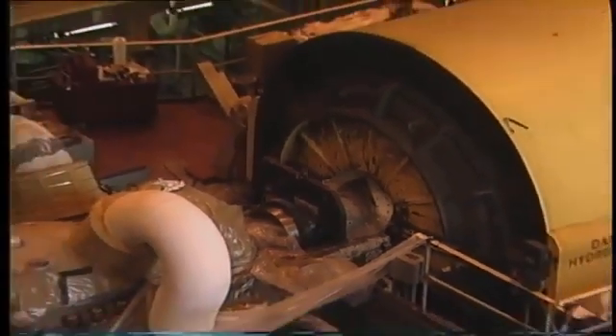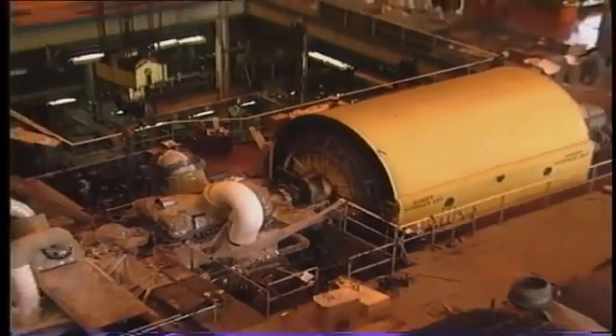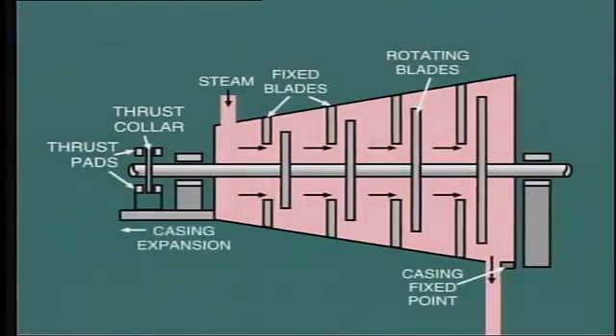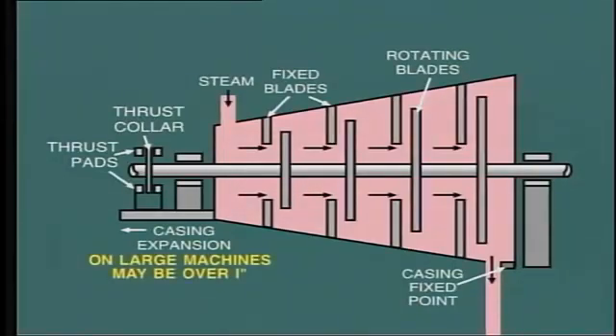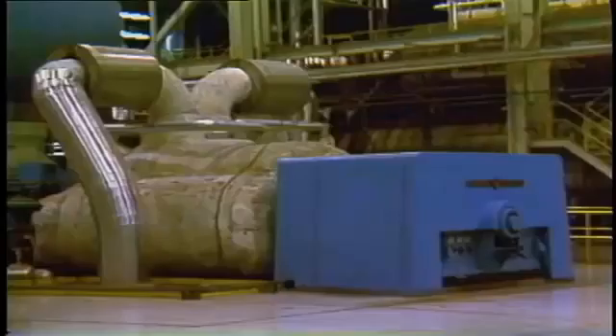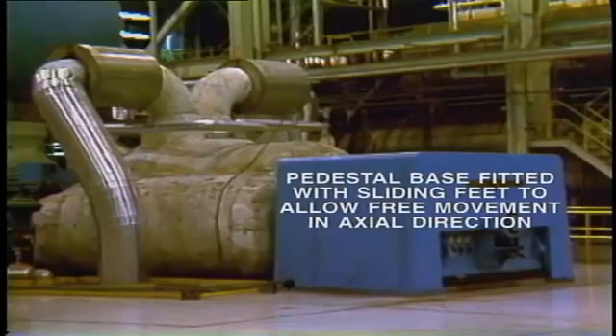During construction and maintenance, thrust pads are carefully set to ensure that correct clearances exist between rotating and stationary parts. Allowance must be made for the casing to expand as it becomes heated by the steam flow. In a single cylinder machine, the normal method is to anchor the machine solidly at the low pressure end—at the turbine exhaust—and allow the front end pedestal to move forwards. In large machines, the expansion in this longitudinal direction may be over one inch, that is 25 millimeters. A more common arrangement on larger machines is to fit the base of the pedestal with sliding feet to allow free movement in the axial direction.